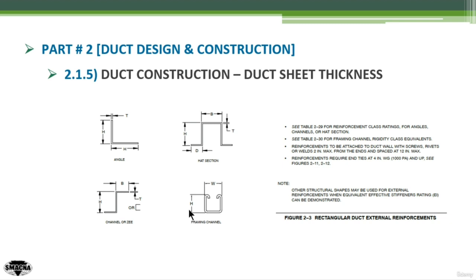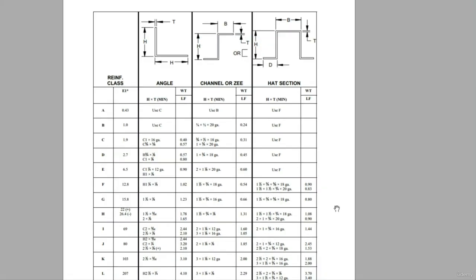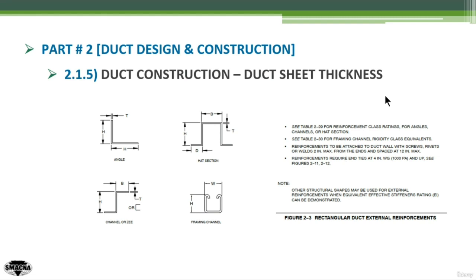These reinforcement approved shapes have dimensions. The following dimensions are given here by letters, and you can obtain these dimensions from the tables in SMACNA for rectangular duct reinforcement. As we can see, these tables are shown here in SMACNA — for example, the L-angle, the Z-shape, the hat shape. There is a reinforcement class which we have spoken about earlier, and this covers the angle details, the channel or Z-channel details, and the hat section details. From these tables obtained in SMACNA you can get the reinforcement details.